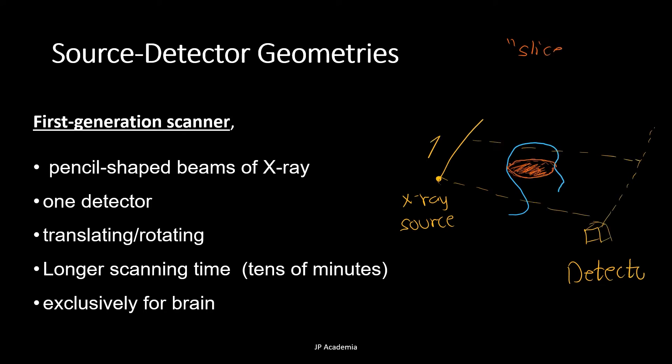So this is called the first generation scanner, illustrated here in the drawing at the right. So this is described by a pencil-shaped beams of X-ray. So let's say we have this X-ray source, then we have this pencil beam. We have this single detector, then it translates before it rotates to another angle. This type of scanner, we have longer scanning time, about tens of minutes. And this is used exclusively for brain.